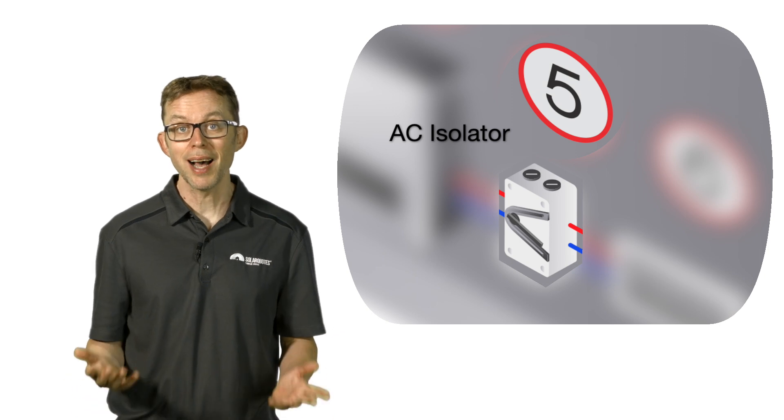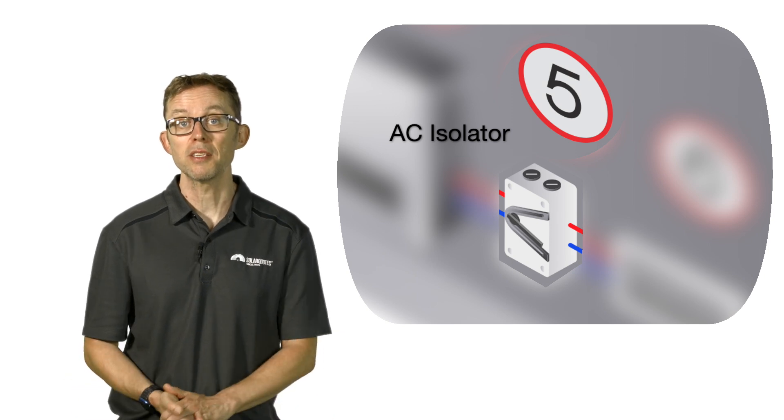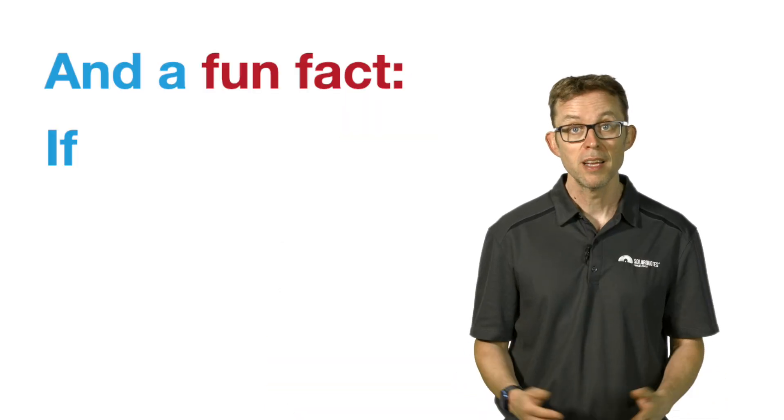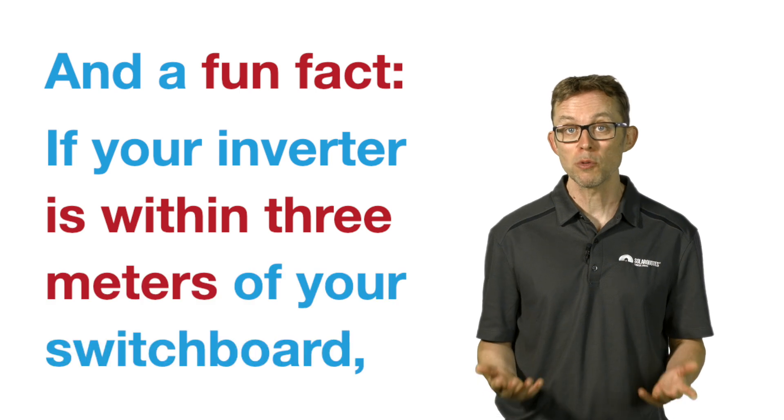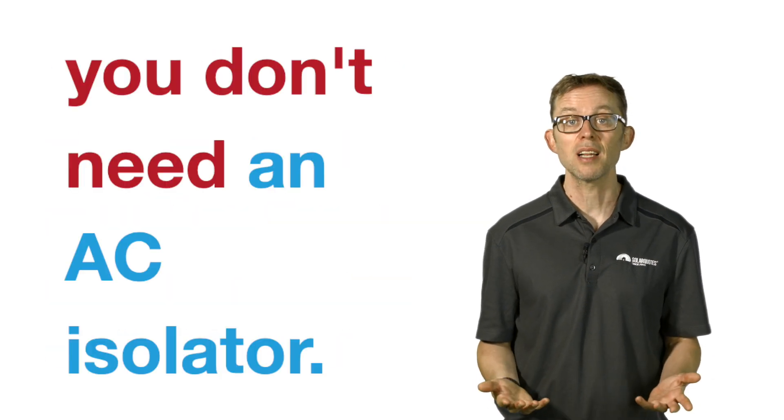If you need to switch off your solar system, you should always turn off the AC isolator first. And a fun fact: if your inverter is within three meters of your switchboard, you don't need an AC isolator. This is because you can isolate the inverter through its switchboard circuit breaker.